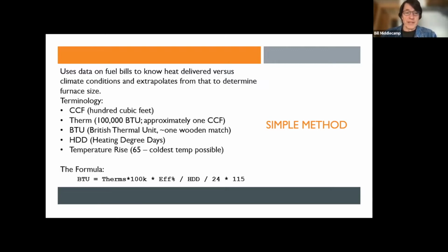So the formula that I used to calculate the size of the furnace that I needed was simply to take the number of therms that are stated on my bill times 100,000 to come up with BTUs, times the efficiency of the furnace, divided by the heating degree days. This gives you the number of BTUs you need per heating degree day. And since furnaces are measured in BTUs per hour, I divide by 24.